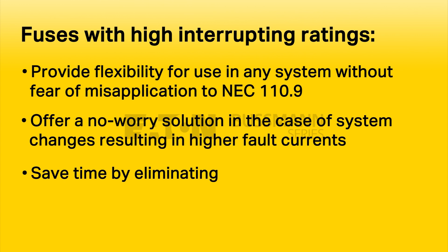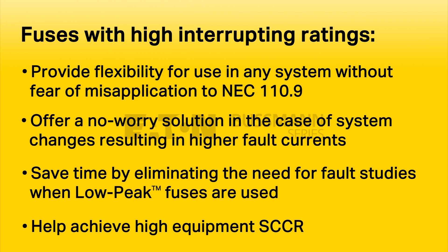Time is saved by eliminating the need for fault current studies when using 300 kA interrupting rating low-peak fuses. Also, high interrupting ratings help achieve high assembly short-circuit current ratings, as the fuse will not be the limiting factor. Modern fuse designs are current limiting. This helps enhance workplace safety by reducing the incident energy and arc flash hazards personnel may be exposed to under fault conditions. It protects components and equipment from extreme thermal and mechanical forces associated with a fault event. This helps with compliance to NEC 110.10 by protecting equipment and components from extensive fault current damage when properly sized.